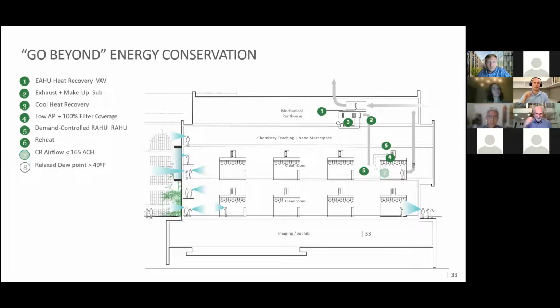Another innovative aspect is we actually put reheat at the little recirc units that blow air through the clean room. The big advantage is that you don't have to reheat all the air at the big central air handler, which wastes a huge amount of energy. You can keep that nice cool air that you've dehumidified and then tune at every zone where you need that additional reheat.